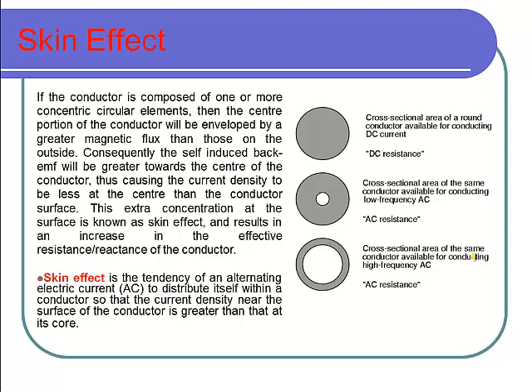That is why in laboratory experiments, when calculating resistance — for example, when testing a motor to find armature or field resistance — you give DC supply and calculate a DC resistance value. But for AC, the effective resistance is 1.2 times your DC resistance. The main reason for this factor is the skin effect.